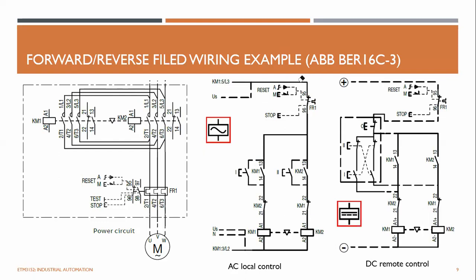Now what we can see here, let's say someone has pressed this forward or the reverse one, right? Let's say this one is pressed. If this is pressed, you can see this is closed. No one has pressed the stop button, so the power comes from here, goes from here, goes from here. KM2 normally close contact, it will be this one, KM2 normally close contact 21 and 22. See 21 and 22, and goes to A1 and A2 of the KM1 coil. This is the KM1 coil, and this is its A1 and A2 terminals.